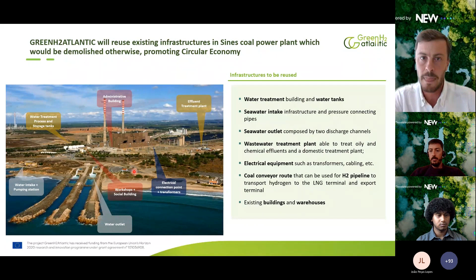A little bit more in detail on the technology that will be developed. We have a dedicated partner, which is also a partner of the Green Deal project, so of the European funded part of the project, which is McPhy. They will provide a 96 megawatt alkaline electrolyzer. This electrolyzer is composed of 6 modules of 16 megawatt. Each module contains 16 stacks of 1 megawatt each, and each stack is arranged in clusters of 4 megawatt.